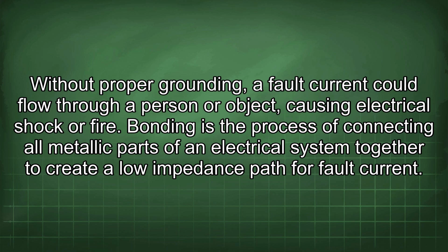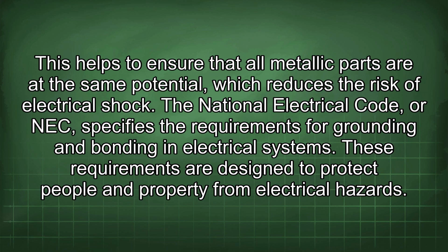Bonding is the process of connecting all metallic parts of an electrical system together to create a low impedance path for fault current. This helps to ensure that all metallic parts are at the same potential, which reduces the risk of electrical shock. The National Electrical Code, or NEC, specifies the requirements for grounding and bonding in electrical systems. These requirements are designed to protect people and property from electrical hazards.